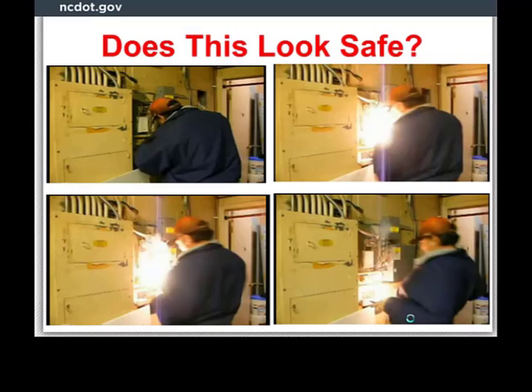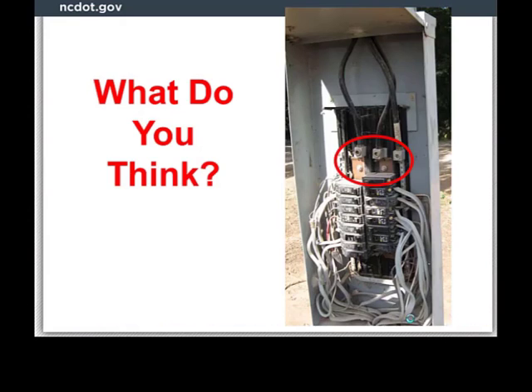Does this look safe? This is probably not uncommon in many places where a maintenance person is troubleshooting or working on energized equipment. So what do you think? Probably at a construction site. Most likely an energized electrical circuit, unless lockout-tagout has been applied to the power source supplying this panel. You can see the exposed bus bars the circuit breakers are mounted to. This is most likely a 120 to 208 volt panel, but if it were 480 volts, an arc flash hazard would definitely exist. I'm showing you this photo to give you an idea how easily a short circuit across hot wires or to ground could happen if you are working on this panel hot or troubleshooting it with a voltmeter.